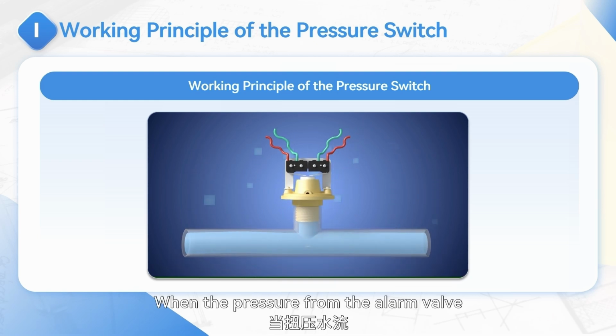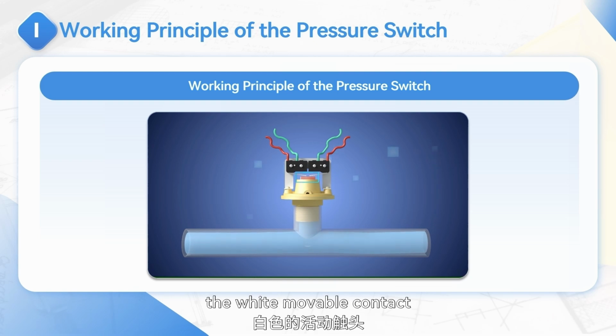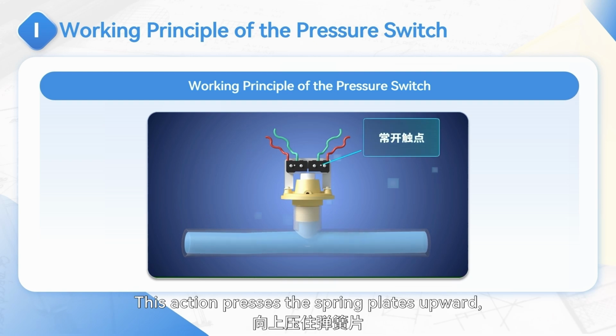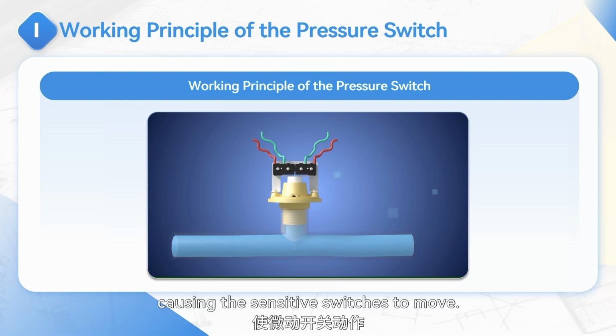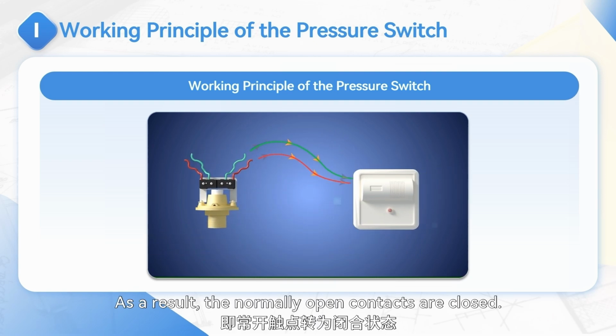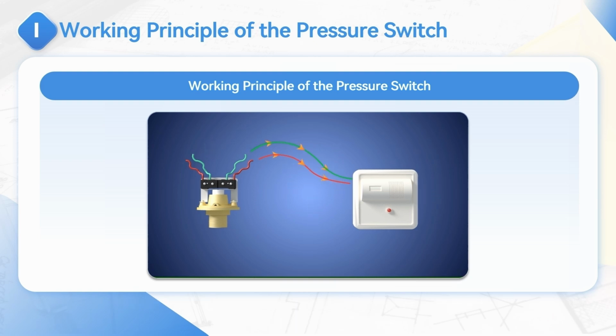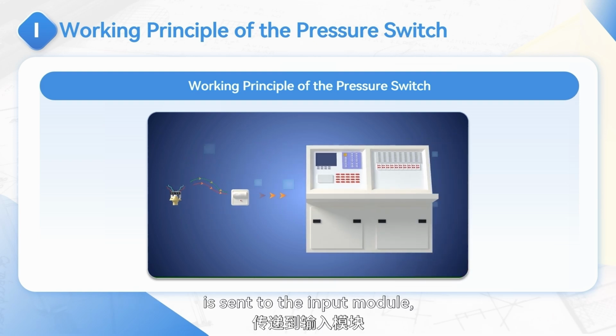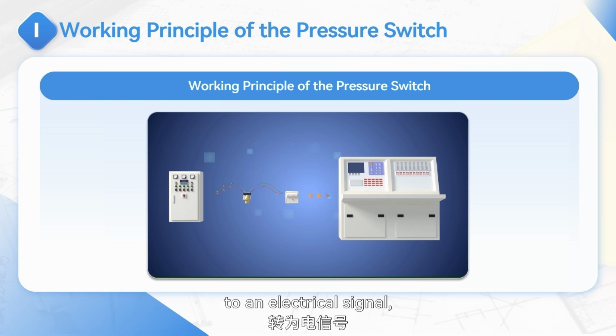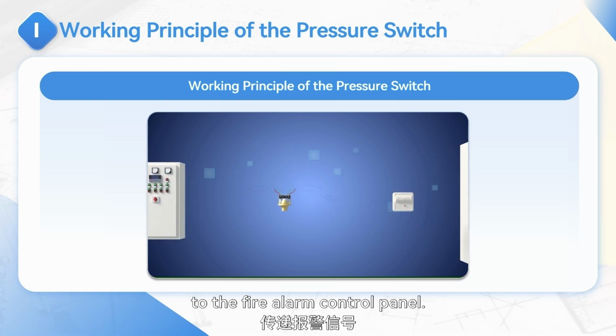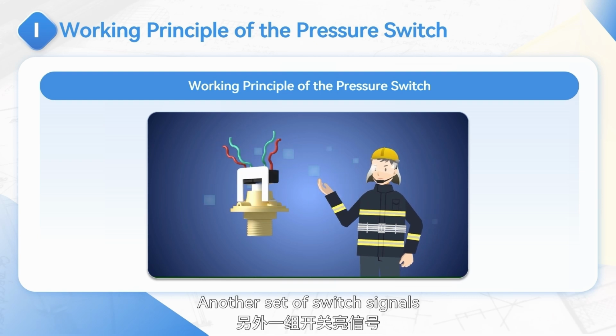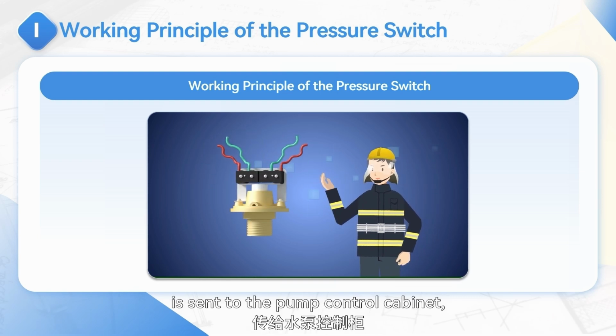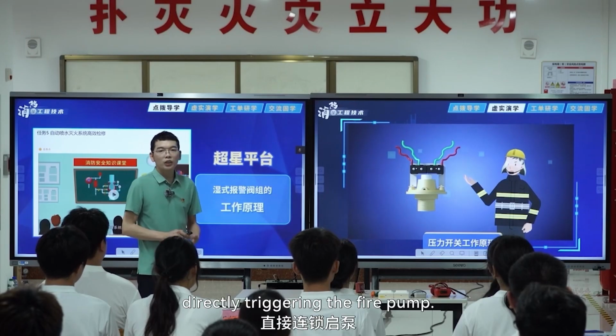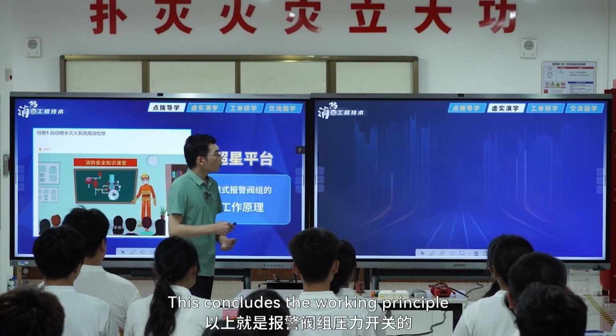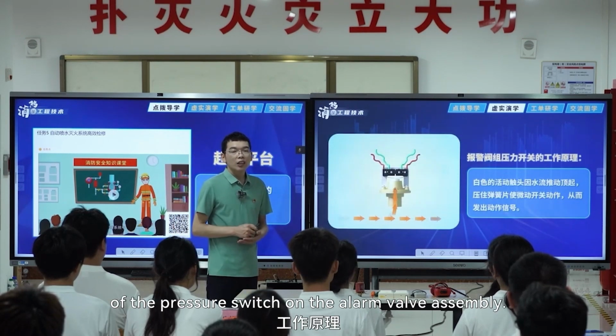When the pressure from the alarm valve activates the pressure switch, the white movable contact is pushed up by the water pressure. This action presses the spring plates upward, causing the sensitive switches to move. As a result, the normally open contacts are closed. One set of switch signals is sent to the input module, converting the water pressure signal to an electrical signal and sending an alarm to the fire alarm control panel. Another set of switch signals is sent to the pump control cabinet, directly triggering the fire pump. This concludes the working principle of the pressure switch on the alarm valve assembly.